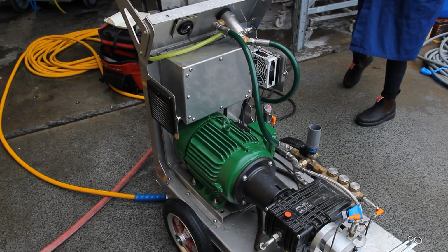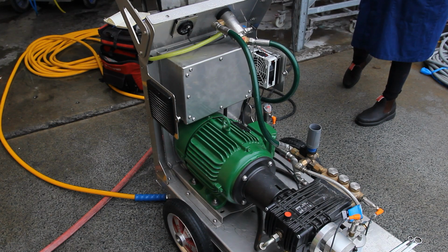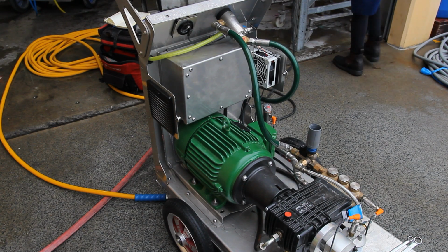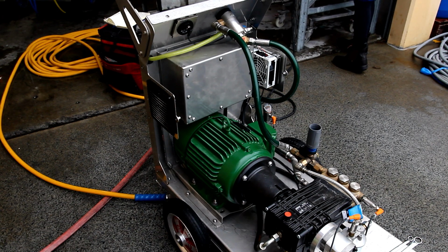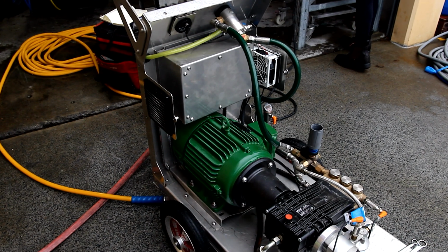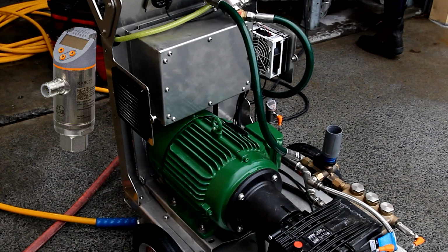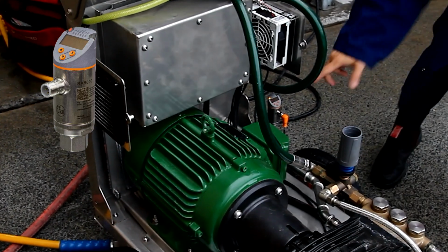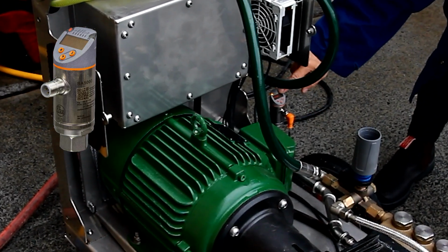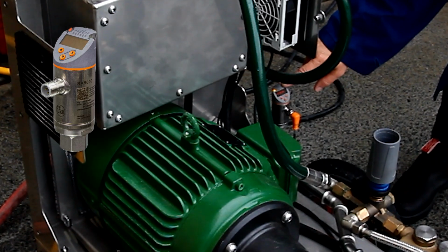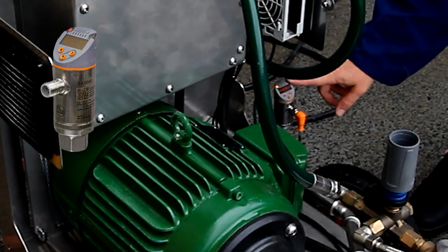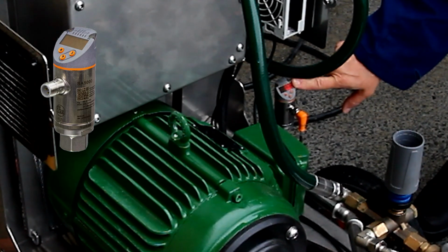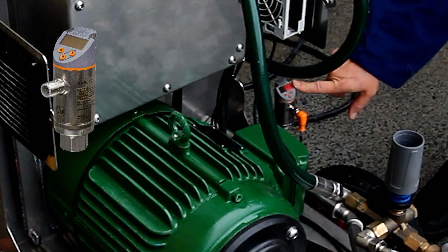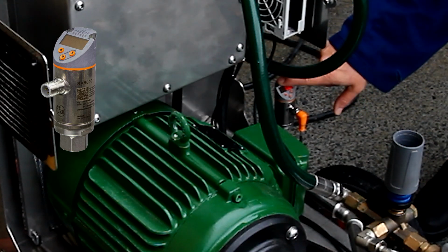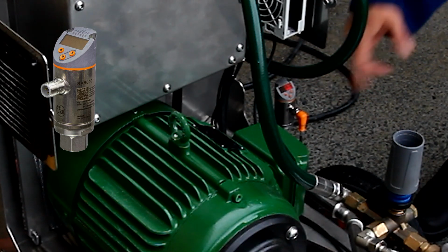Okay, so we're going to depower this machine now and then repower it, because I want to show you the 10-second warm-up for the flow sensor. I'm just going to turn that off. Hone in on that flow sensor. Turn it back on. So you'll see here the light comes up. The flow sensor is warming up, goes for about 10 seconds. Okay, then we've got our reading, 0, 0, we have no flow. There's no light on, we have no flow. So I'm going to turn the water on now and then you'll see the flow.